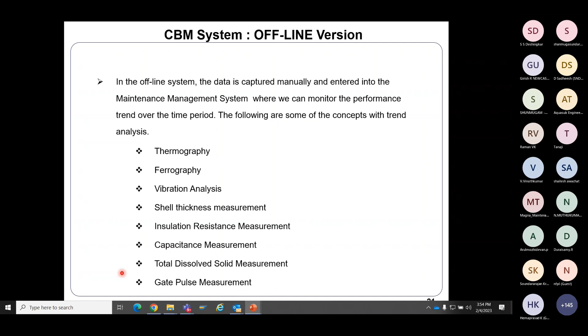Capacitance measurement: in most of the equipment, the melting equipment, you will have a lot of capacitor banks connected. Usually only upon failure of the capacitor will you try to replace it. People may look at the capacitor to see whether it is bulged, which is a physical analysis. You may use thermography as well. You may use capacitance measurement by which you can decide whether the capacitor requires replacement or not. Then total dissolved solid measurement. Then gate pulse measurement; these are gate pulse measurements specific to melting furnaces.